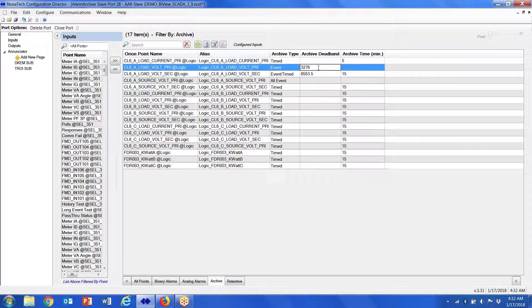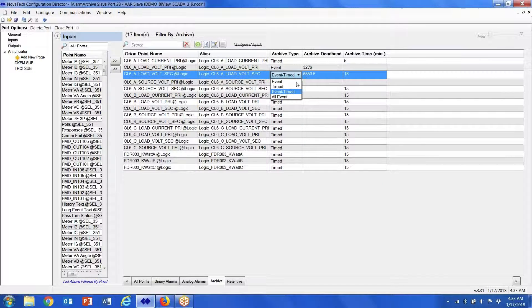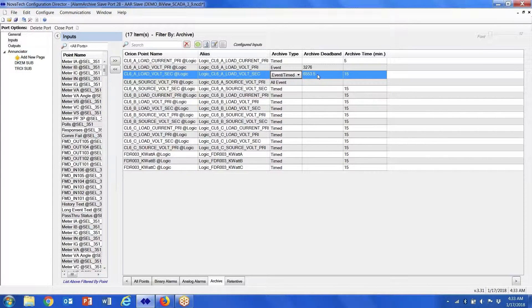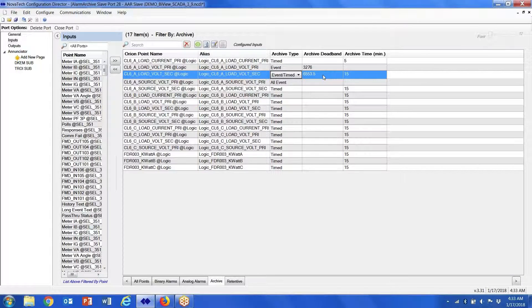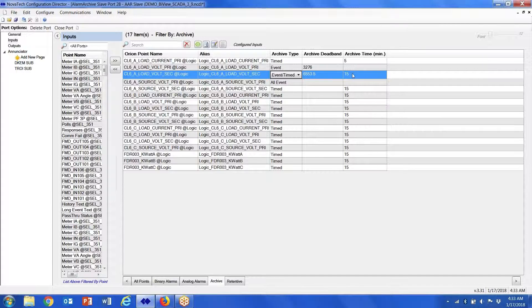For event and timed, it's going to get archived based on a change in deadband. If the deadband never occurs, then it's still going to get archived every 15 minutes.